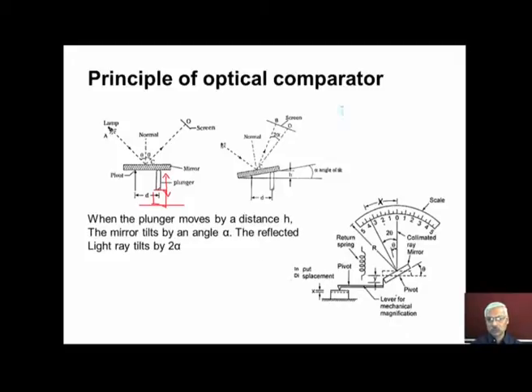This picture shows the general arrangement of an optical comparator. We have the table surface and the workpiece. Depending upon the heights of workpieces, we have the input displacement x, which is the deviation from the desired size. We have a lever with a pivot, where one end is in contact with the workpiece surface and the other end is in contact with the mirror. So when the pointer end of the lever moves by a distance x, the other end moves by a distance y because of this mechanical amplification.